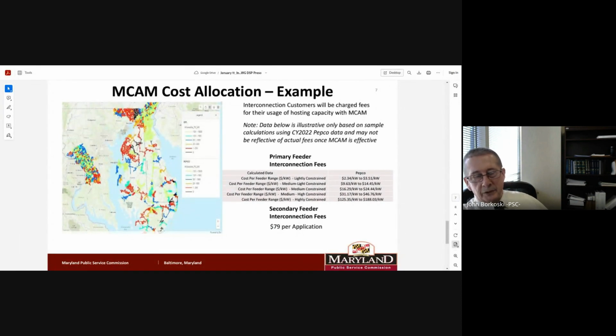So we don't want just one static 3 megawatt level, but we do want some level of reserve hosting capacity, because we never want a situation where a residential customer can't interconnect. I feel that was reinforced at the hearing on Tuesday when the commission approved the regs, including the CCSA recommended additions to wording that really require utilities to do this on a circuit-specific basis.